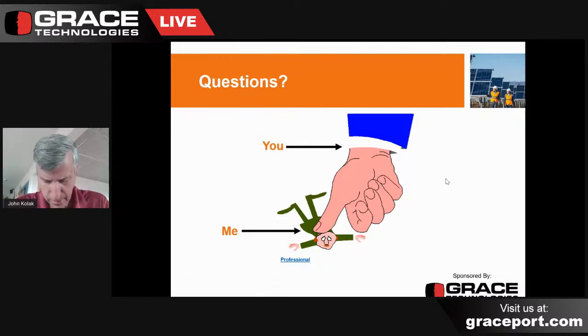So the first one is, what are the PPE category levels as per incident energy levels for DC systems, or the same as AC? Yeah, the calculated incident energy, you're going to use the same values. It's just going to calculate differently. So the software now will give you calculations on DC systems. You may have to interpolate a little bit about that, but whatever the calorie number calculates out, DC or AC, you're going to use the same kind of protective equipment.